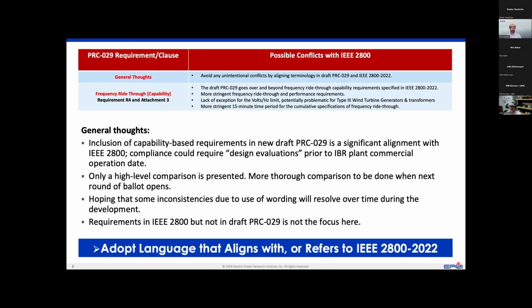We believe that this is a good approach because by the time an IBR plant enters commercial operation, it is often too late to make any design changes. And if the equipment used in the plant does not have those capabilities, it may not have them during its lifetime. So looking into that during the design stage of the plant does seem like an important consideration. Now, we really only presented a high-level comparison here.